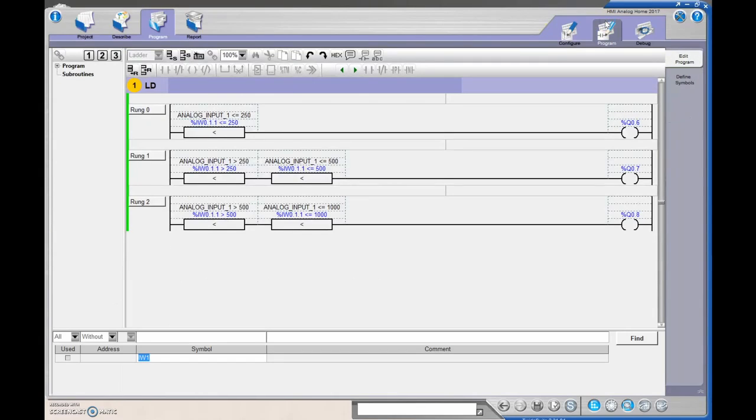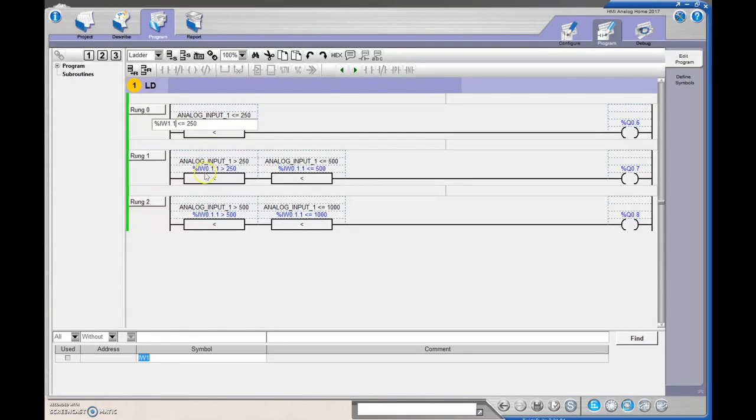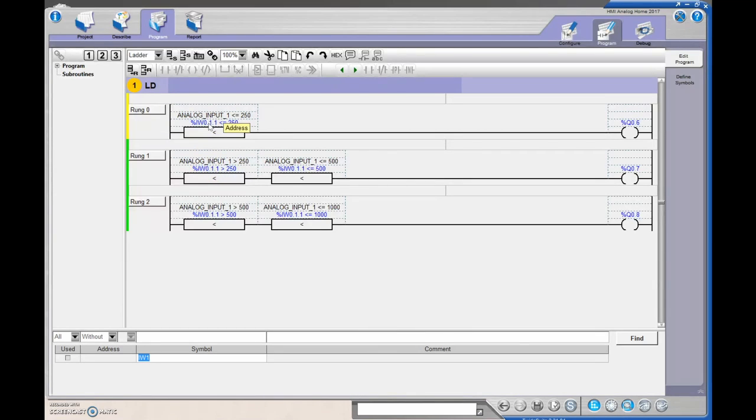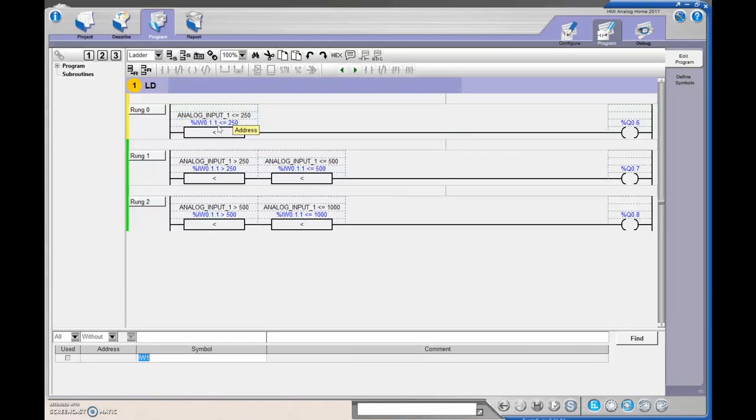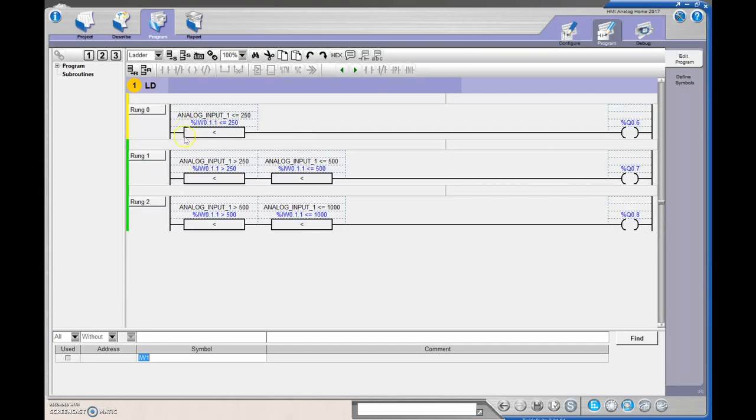With the program, I've put in, and watch this, I've done %IW1.1. When I hit equals, you'll see that it changes the value to this. So let me hit equals here. As soon as I change that and hit enter, it changes it to %IW0.1.1, that's the appropriate address. I thought that was why I wasn't seeing my 0 to 10 volts, but it wasn't. It was the fact that I didn't give this guy my analog card 24 volts DC.